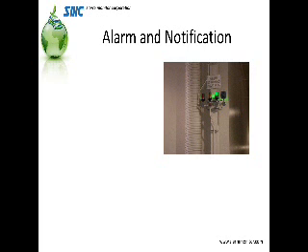If the mitigation systems, exhaust and makeup air, eliminate the gas, the green light will come back on, meaning the level has now dropped back to a safe level, but the red light will stay on, indicating that it's latched, continue to keep the mitigation going, and horns remain in the building. The first responders then will know that the area is now safe to go in, to check for the leakage, and to clear the system for the return of the occupants.